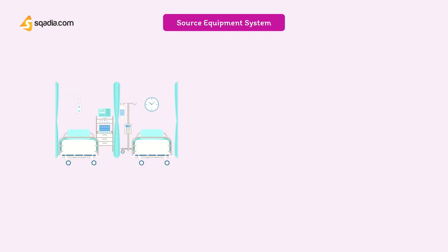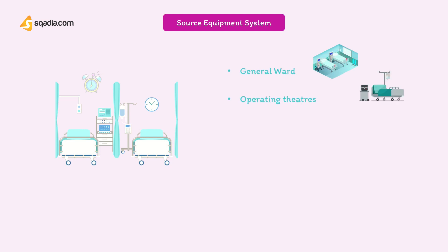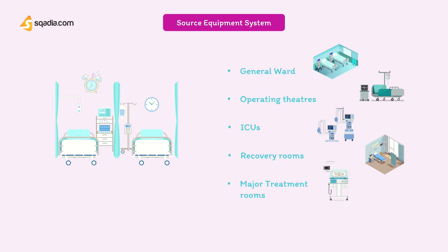Source equipment systems are generally required to be monitored by alarm systems at the point of supply for abnormal gas pressures in areas such as general wards, operating theaters, intensive care units, recovery rooms, or major treatment rooms.